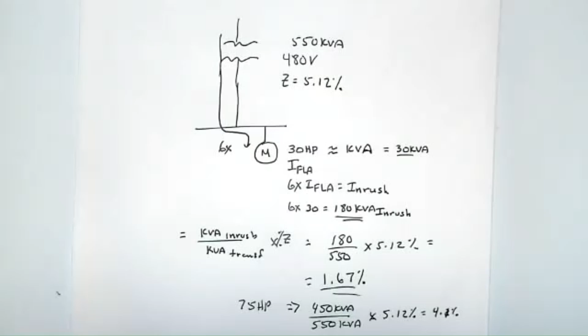So again, in this case, we have a little bit more inrush current because the motor's bigger. We have about 450 kVA worth of inrush kVA. Compare that to our 550 kVA size of our transformer. You ratio that and look at the impedance, and we get about 4.1% drop. Now, again, that doesn't really require formal analysis, but we will see that in terms of light flicker. And so again, if the motor was starting many times a day, you might get more of an inrush effect in terms of people noticing and maybe problems associated with that.